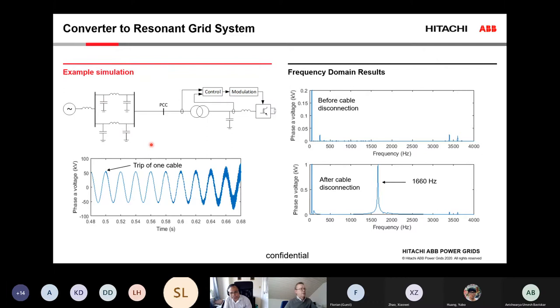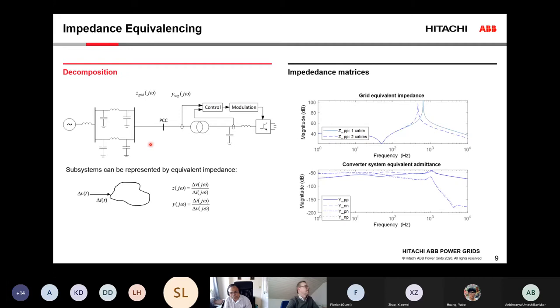So how do we analyze these things? For the understanding, impedance equivalencing is a very, very useful tool. Impedance equivalencing can be used to represent a part of the total system, either the grid side or the converter side, as an equivalent impedance. So we can look at the PCC and simply measure the impedance seen to the left to get an impedance equivalent of the grid, or we can measure the impedance to the right to get an impedance or admittance equivalent of the converter system.